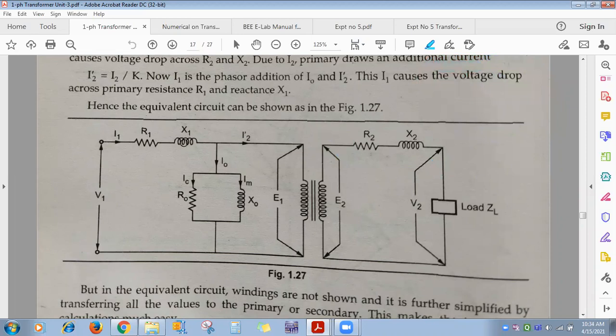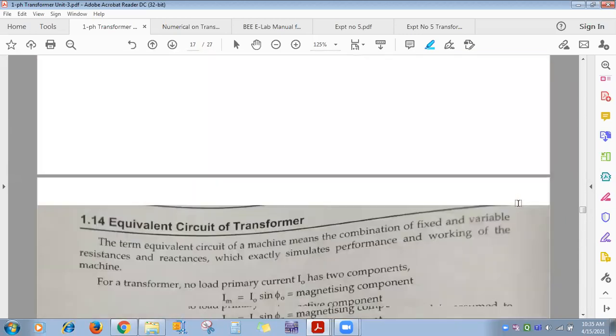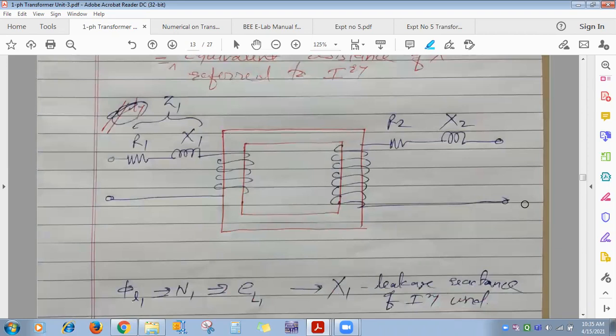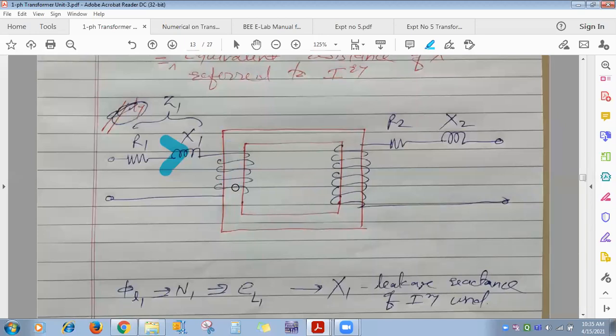X1 and X2 in the equivalent circuit represent leakage reactances. AC current through the primary winding produces alternating flux; 95–98% flows through the core as useful flux, but some completes its path through air — this is leakage flux.